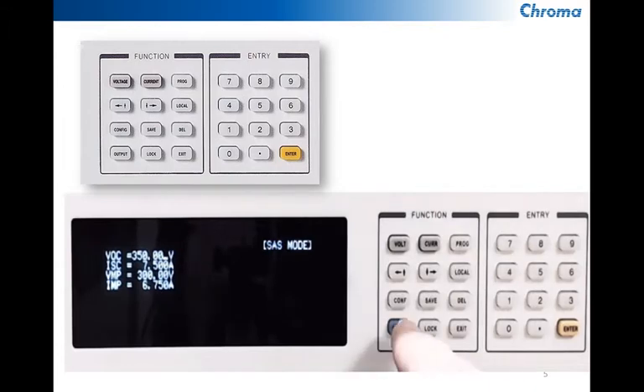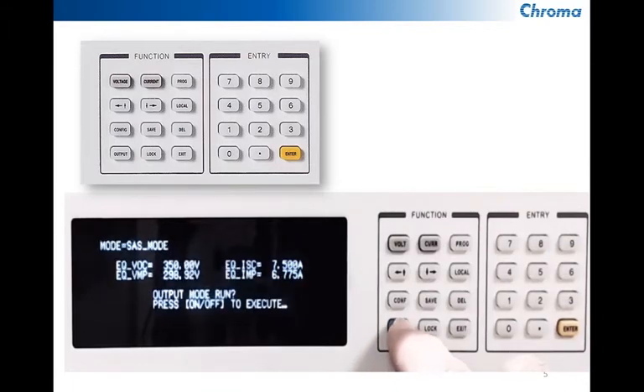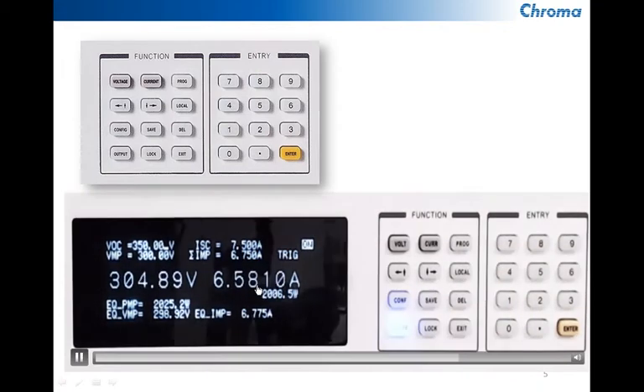Once we've done that we can connect the unit to the inverter input and then we can press the output button. And from there you'll see that when we run the output by hitting execute it'll give us the voltage and current at maximum power. It'll also show the parameters that we use to set it. It'll tell us the output is on and it'll give us the equivalent power of 2,025 watts and equivalent voltage at maximum power and equivalent current at maximum power as well.